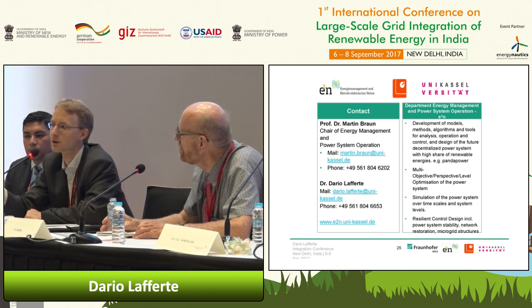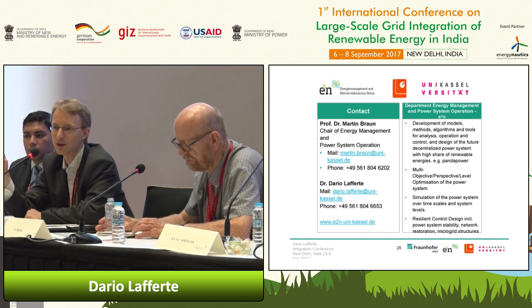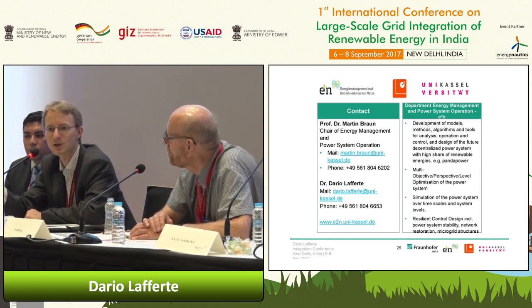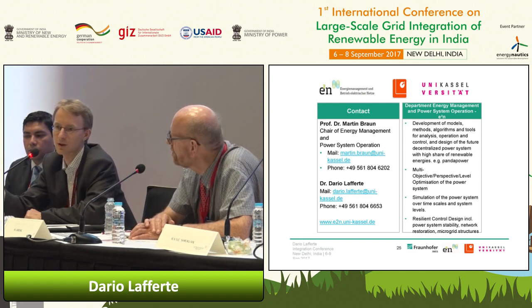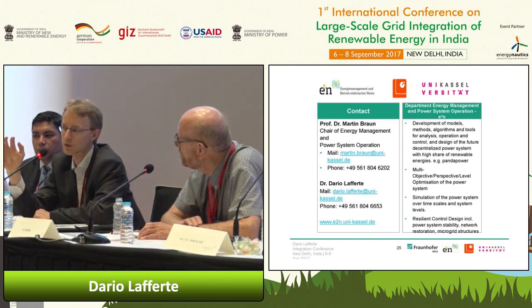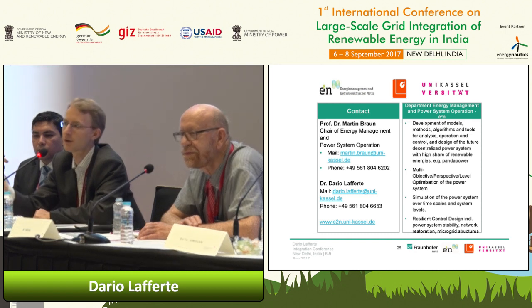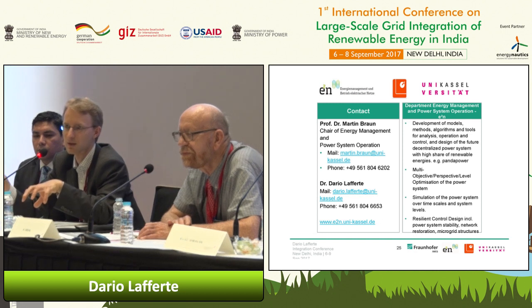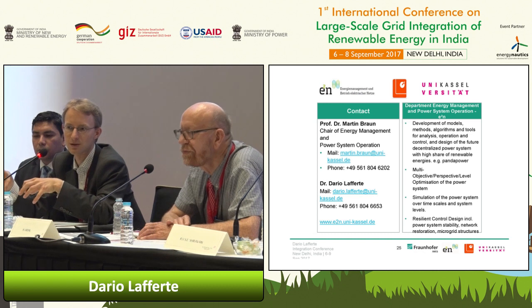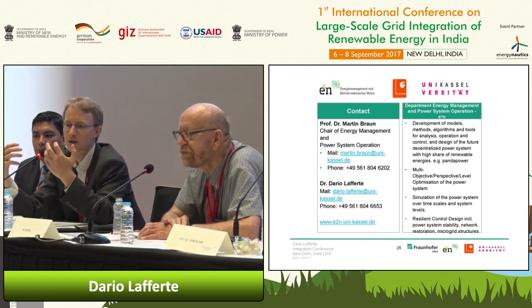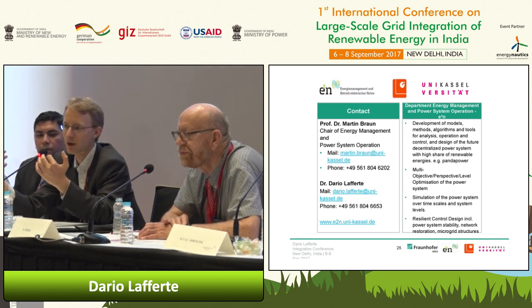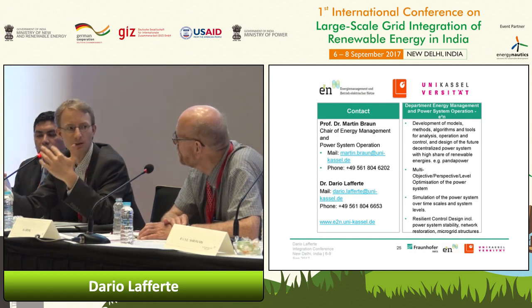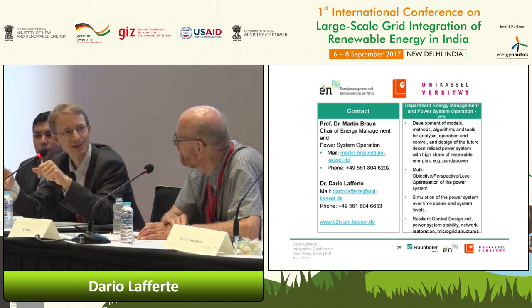Now we have been talking about very small island systems, so we're looking at some low voltage system or extended with medium voltage. And there, I think it doesn't make much sense at the very beginning to have synchronization devices all the way, but it's a starting point, so we are now just looking. There's also another work to analyze what the applicability is throughout the grid, because you need to have certain grid-forming capable units, and you need to have sufficient generation available. So you analyze where you can actually build islands like that, and then you have to think about whether it makes sense to build islands in parallel and synchronize them. So there are different ways. Here the first starting point is: using the renewable energies available in the distribution grid, can I build an island? And if it's possible and we see that it's replicable and scalable to a larger degree, then we need to think about the synchronization issue in more detail.